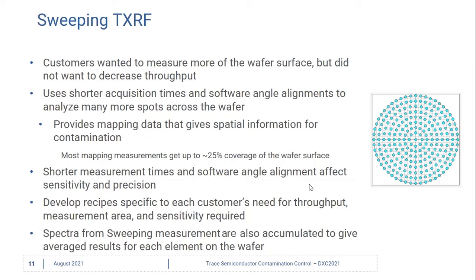Customers wanted to know more about the contamination on their wafer surface outside of the three to five measurement points in the traditional TXRF measurement, but they didn't want to decrease their throughput. So sweeping TXRF was developed because it uses shorter acquisition times and software angle alignments to analyze many more spots across the wafer, providing mapping data with more spatial information about the contamination.